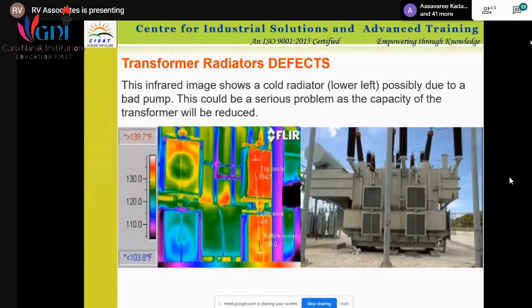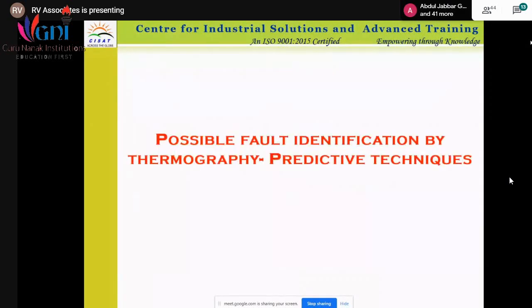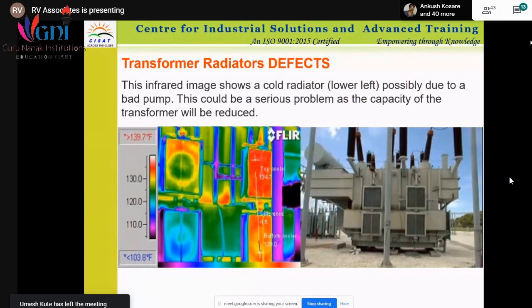These are all practical case studies for the identification of faults. This is thermography, what we say. It is one of the predictive and preventive maintenance techniques for fault identification. It gives you a complete picture of the rise in temperature in any equipment, and it can be used for all electromechanical devices like electrical systems, cable jointing, then motors, motor bearing parts, mechanical systems, joints. In the case of a transformer, bushings are there.